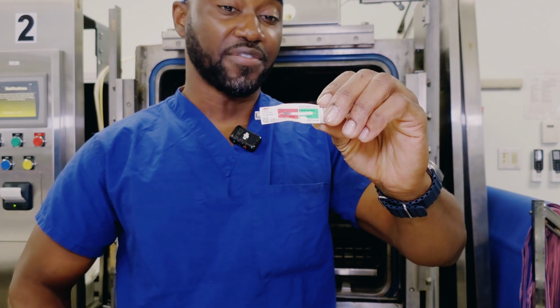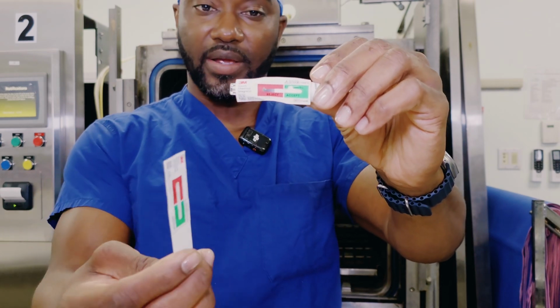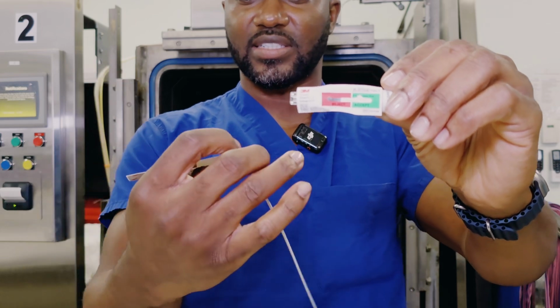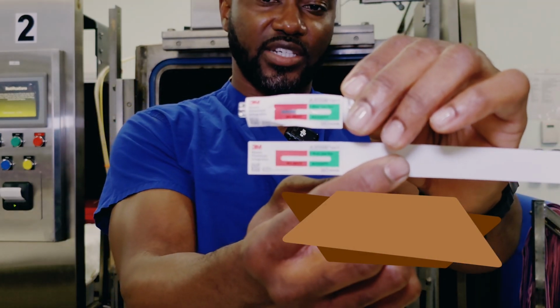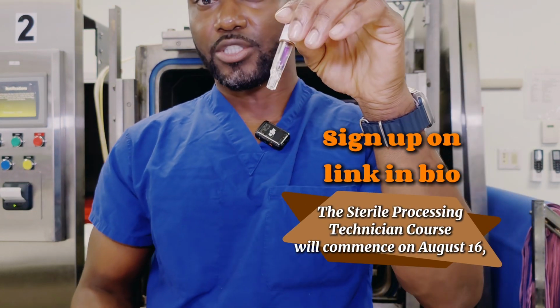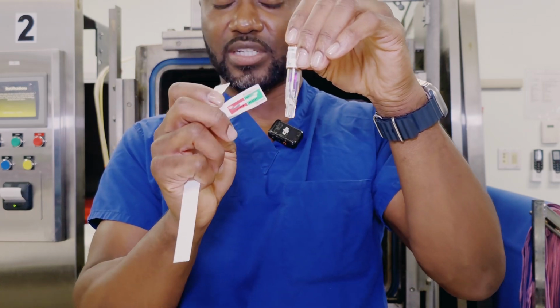We already knew it was going to fail, but we ran a biological anyway. So look to see where it says accept. The black indicator dye should have crossed and gone to the green side, but it did not make it, showing that it's a fail result. So most likely if I run this biological, it's going to show that there's still growth of Geobacillus in here.